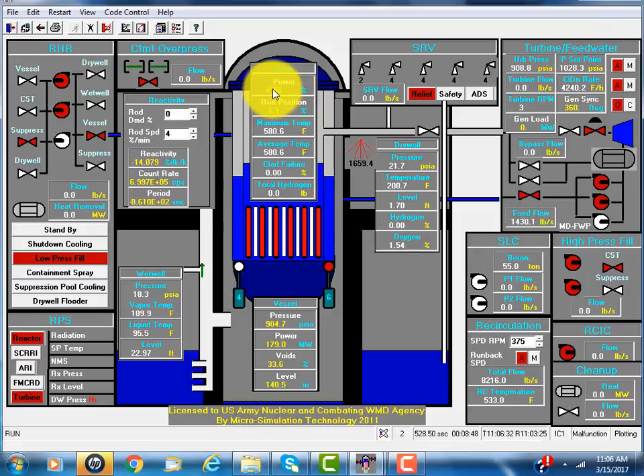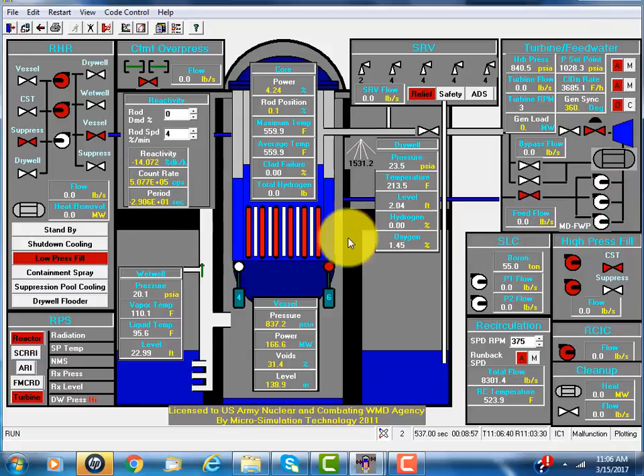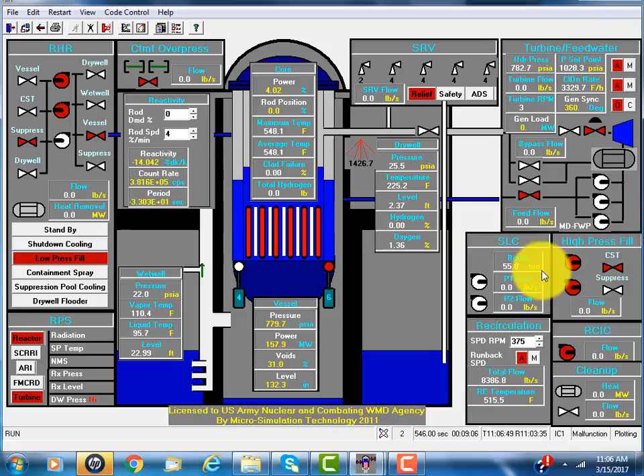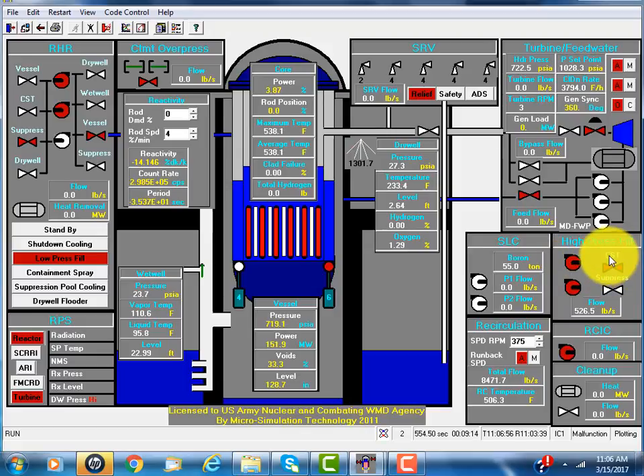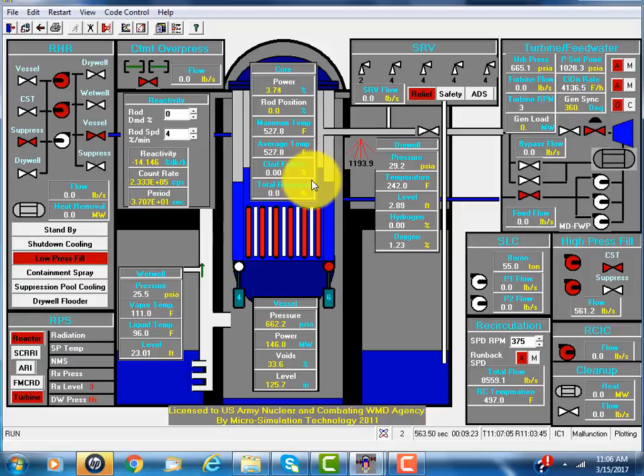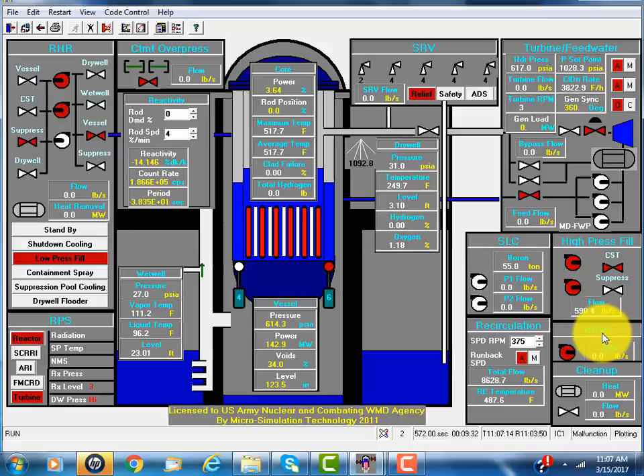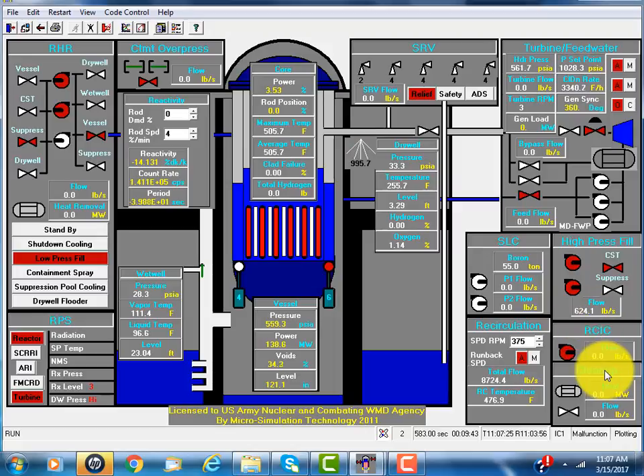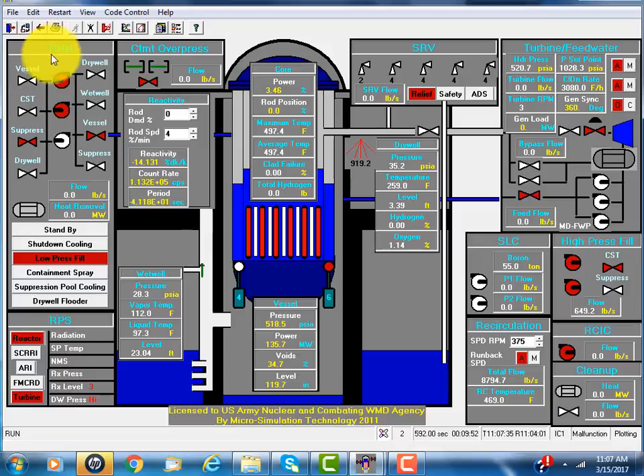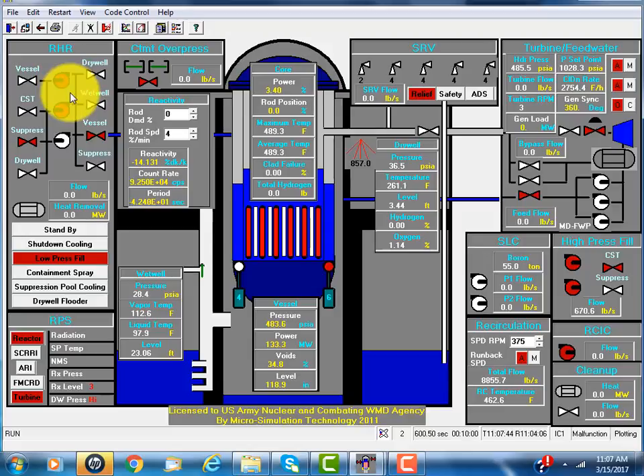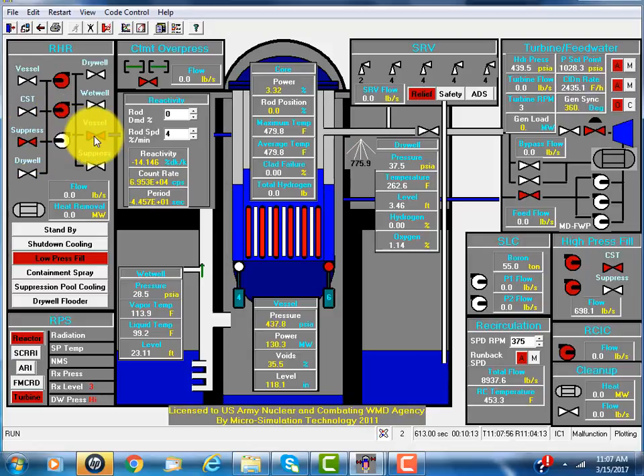Suppose we lose feedwater. There's a high-pressure core flooder for ABWR. The pumps are turbine driven. It takes water from the condensate storage tank and puts it into the reactor vessel. There's another one called reactor core isolation cooling. That's also turbine driven. It has a time delay. The RHR, residual heat removal system, the pump will restart on emergency diesel. It takes water from the suppression pool back to the vessel.